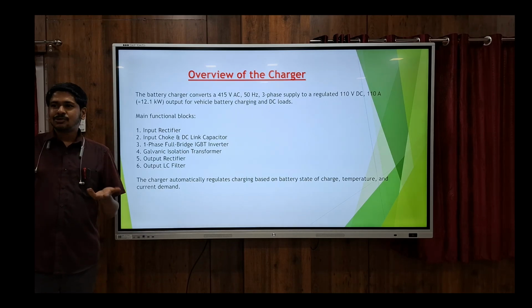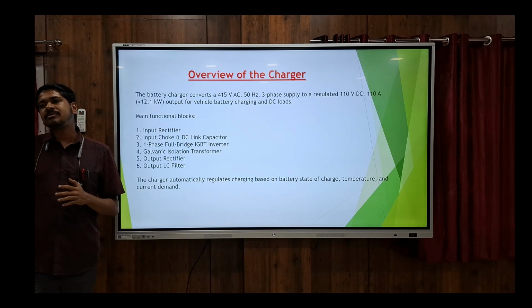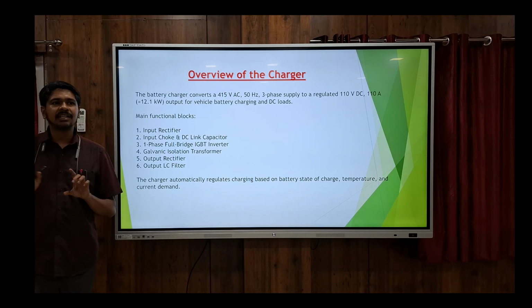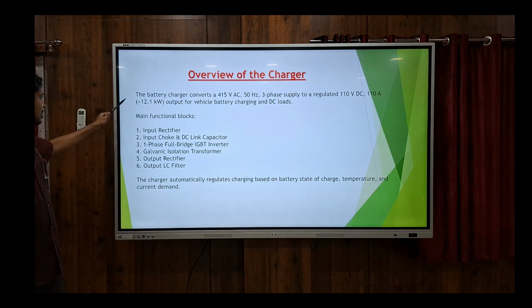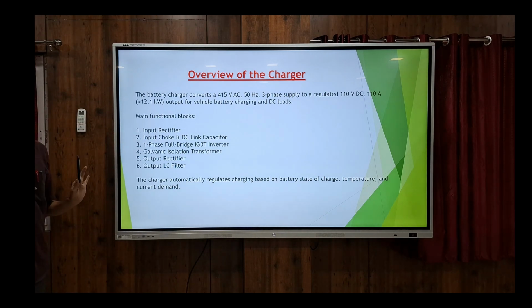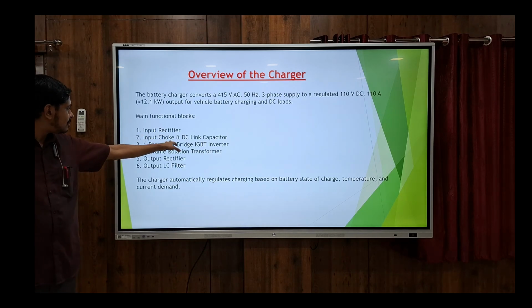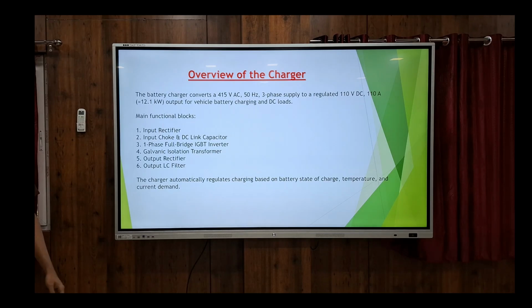Then what is required? Actually, the battery charger is DC, so we are having three phase AC with us. We have to convert it into DC, so a rectification process is required. The initial stage is the input rectifier. Then input choke and DC link capacitor. This three phase supply which is coming from the bar will have a lot of ripples, and we need to hold this power without much fluctuation. For smoothing the current and voltage and giving a constant supply, the second stage is the input choke and DC link capacitor, for smoothing the DC.